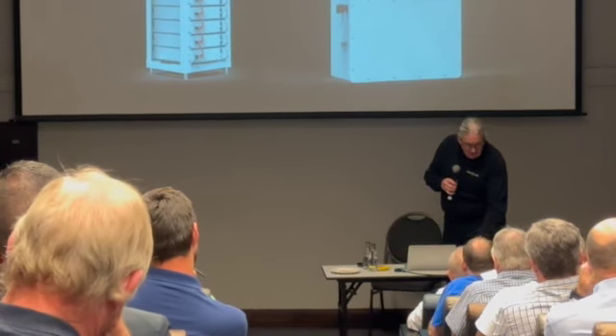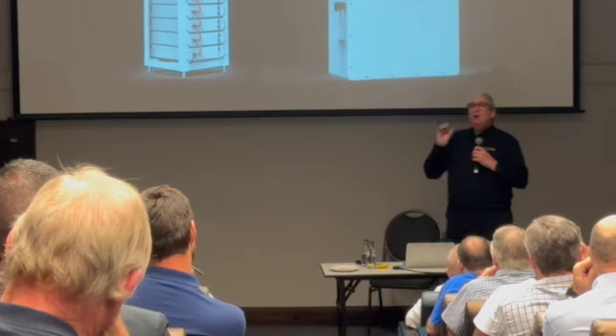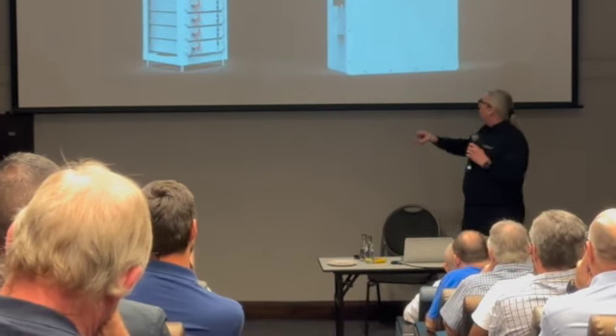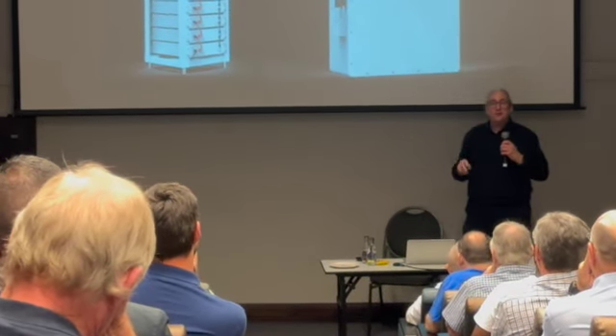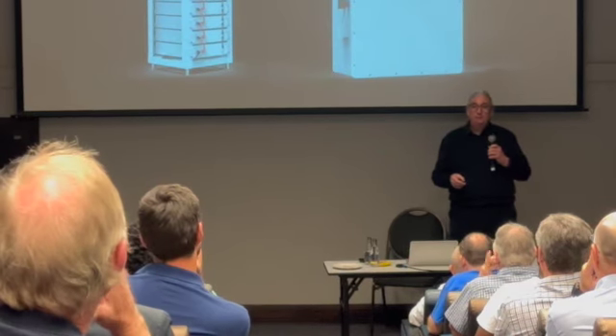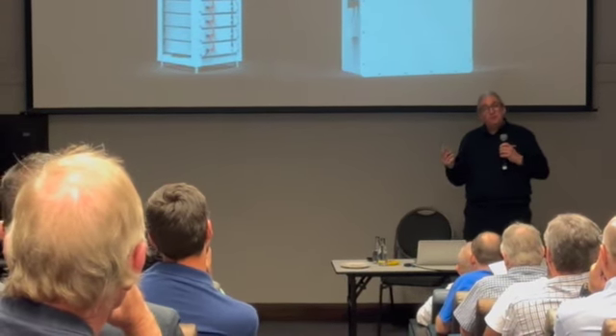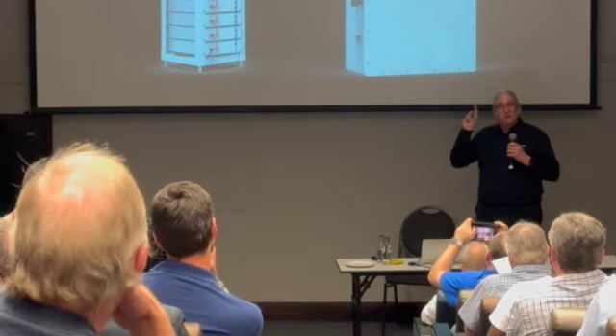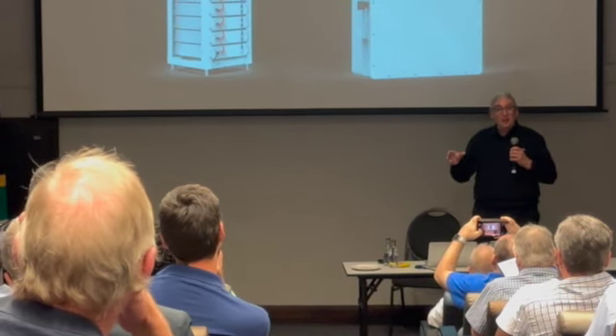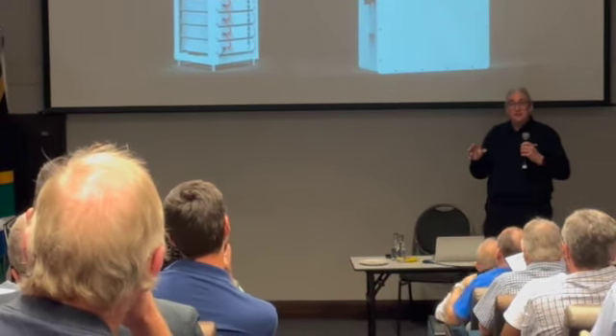Look on the inverter, it's got two channels, as I mentioned before, two channels, two batteries, 100 amp each channel. If you're using a single battery, you must link the channels together, then on the menu select the linked single battery option. If you've got two batteries, select that instead.